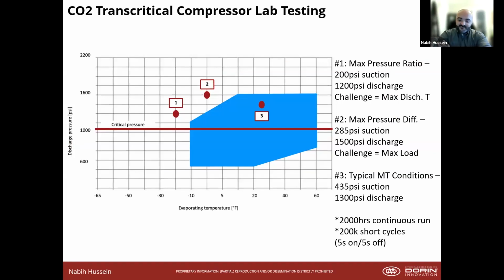We test at three different points to validate our designs. Number one is max pressure ratio, which is the ratio between suction and discharge pressure. The challenge there is you'll see the max discharge temperature at this point. Max pressure differential is the next point we test: 1500 psi discharge, 285 at the suction. The challenge you see is max load. Then we test at typical MT conditions, which I think is the most interesting for people to see. For every compressor we validate, it's 2000 hours of continuous running, which isn't a very long time to run a compressor, but it does remove any youth issues you would see in a compressor's design. And then we run it 200,000 times, short cycling, 5 seconds on, 5 seconds off. So we did our very best to try and destroy our compressors in our factory so it doesn't happen in the field.